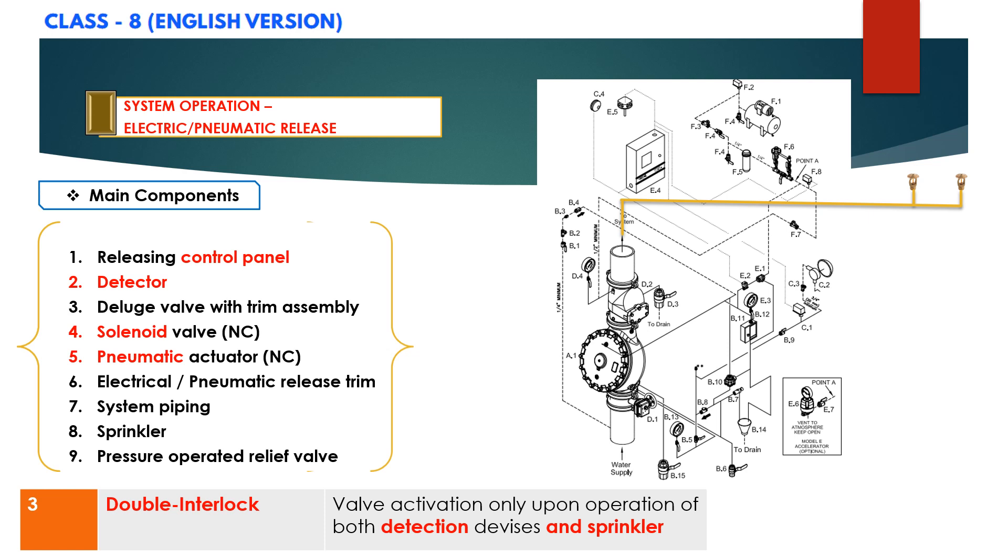Please note that the deluge valve A1 can only be reset after the system has been taken out of service and the outlet chamber of the deluge valve and associated trim piping are depressurized and drained.